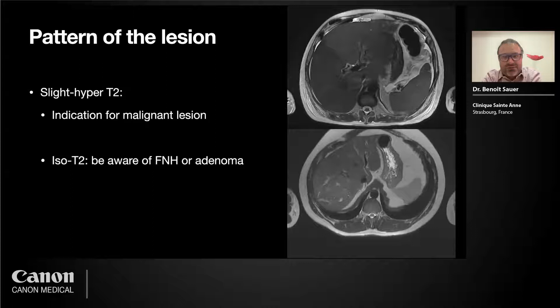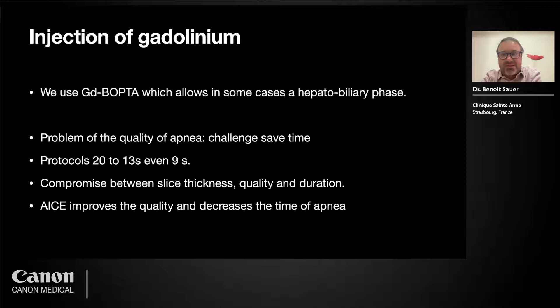Injection of gadolinium, we use gadobopta, which allows us to make a hepatobiliary phase in some cases. It's a problem with the quality of apnea. The challenge is to save time. Each sequence before DLR lasted 20 seconds, but with DLR it's 13 seconds, and we even have a protocol of 9 seconds. It's a compromise between slice thickness, quality, and duration. It's very important for elderly patients.